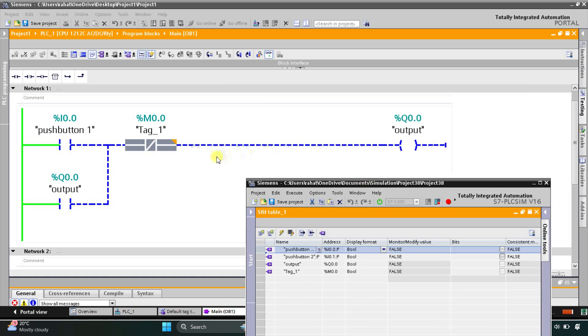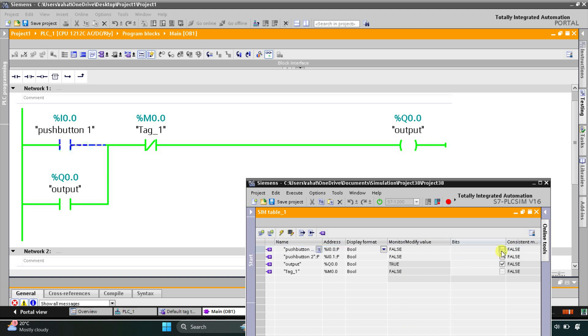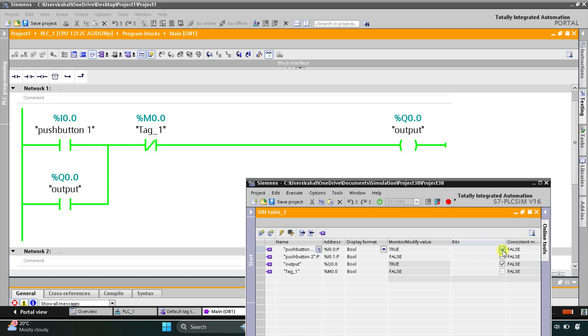As you can see, when I press and release push button one, the output turns on. The current flows through it, and M0.0 is used as a normally closed contact — when it is in false state, current passes through it and the output is true. When I release push button one, the output was already true and the normally open contact latching branch also becomes true, so current continuously flows through it and the output remains on.